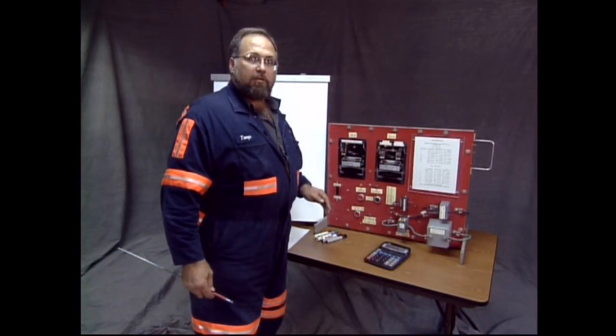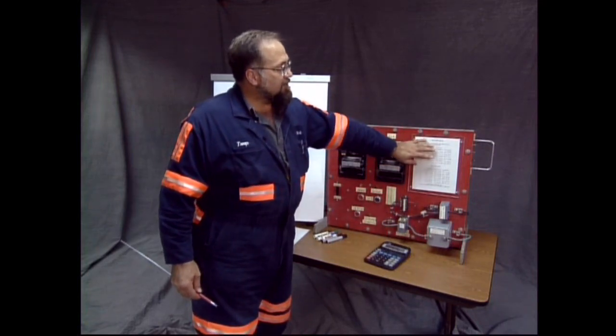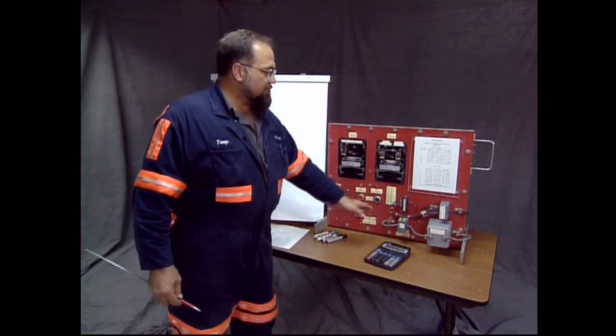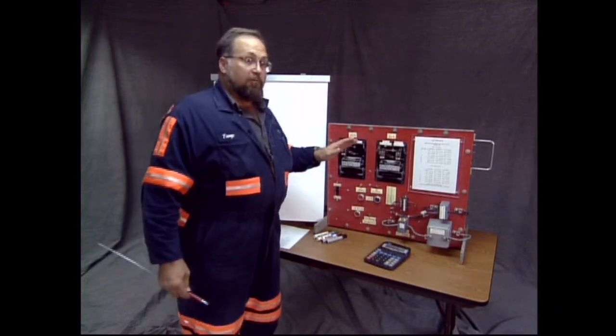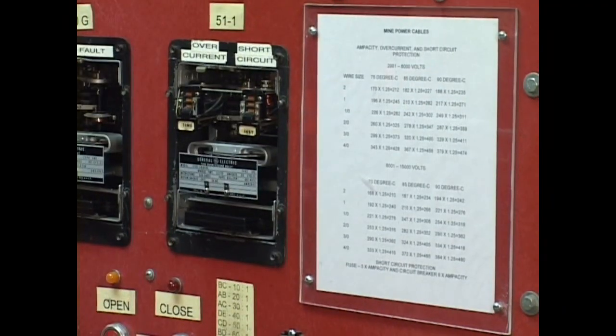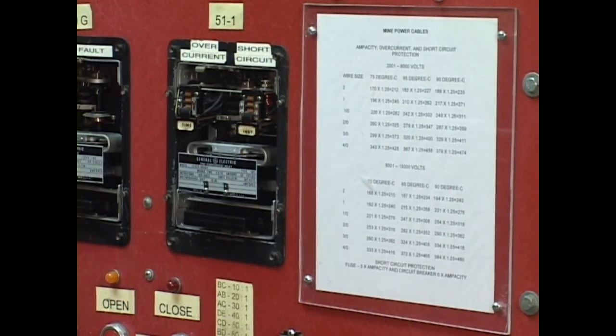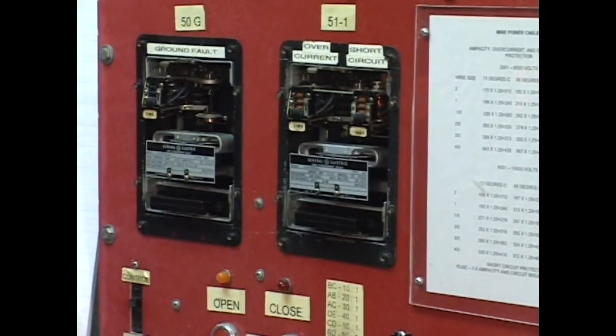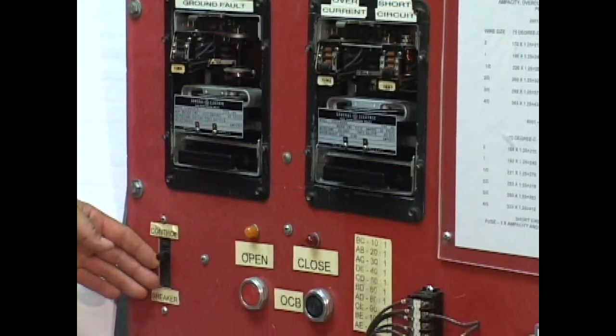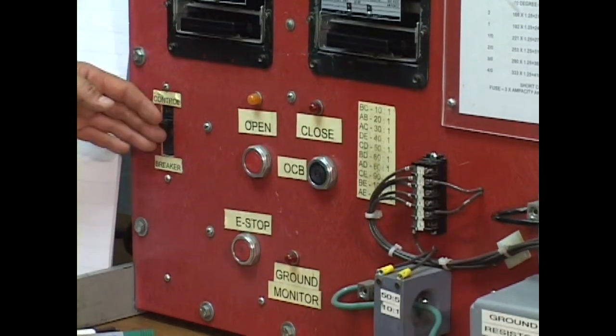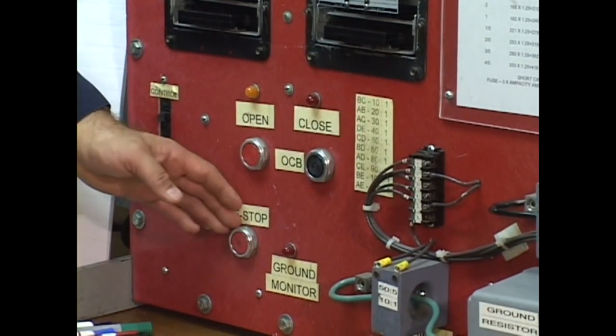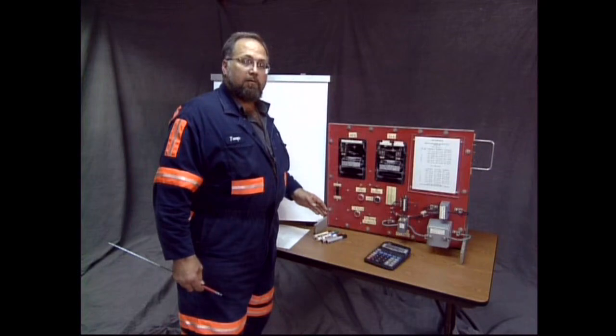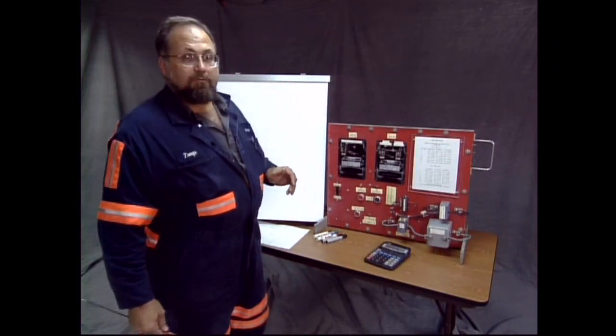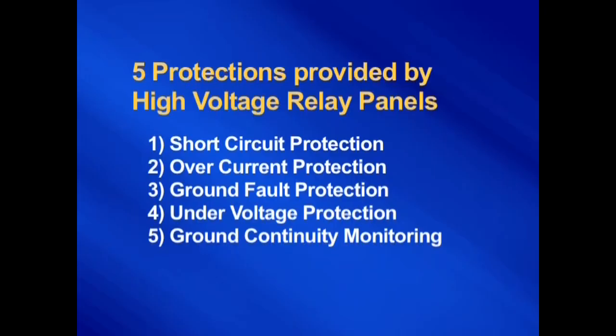You have short circuit protection. I generally start by the chart and work in a semicircular fashion and give myself a visual prompt. You have short circuit protection. You have overcurrent protection. You have ground fault protection. You use the control breaker to prove under voltage protection. And then you have ground continuity monitoring. Those are the big 5. Those are the 5 that you could be asked on your test. What 5 protections are provided for by a high voltage breaker relay panel.